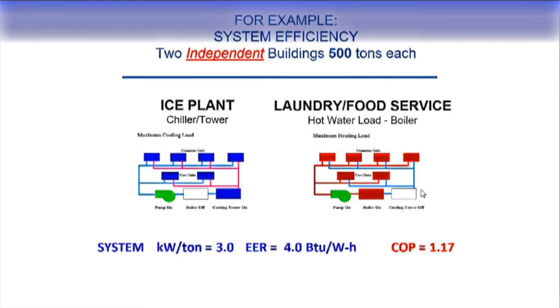Okay, both 500 tons. If I calculate the system COPs, it tells you the parameters. My system is at kW per ton, about 3, and the EER is about 4 in the boxes.